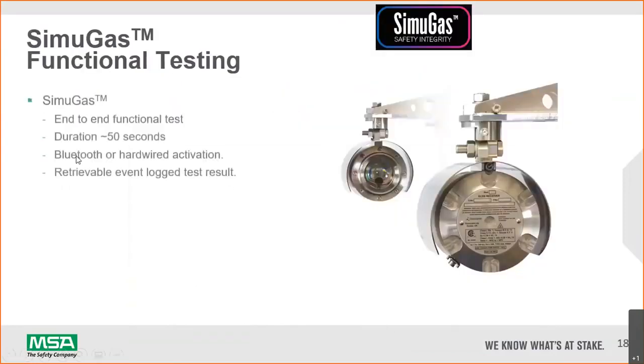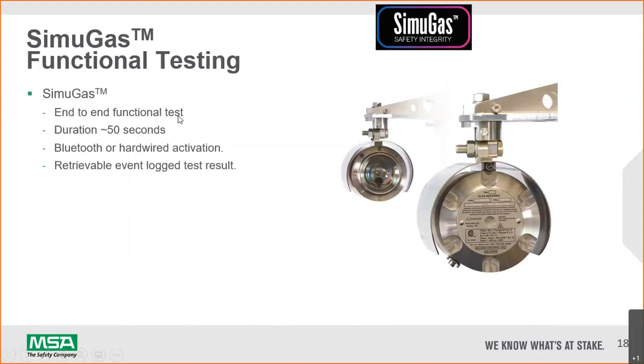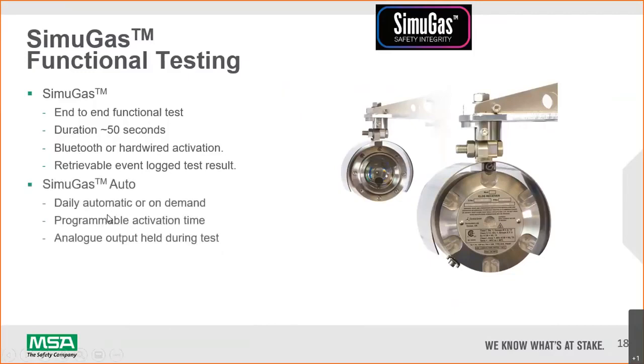This is the SimuGas end-to-end functional test, same like in a piano synthesizer, when you touch a key, it will transmit the same frequency all the time. The duration is less than 50 seconds, with Bluetooth hardware activation and retrieval, that we talked about, SimuGas auto. We call it auto because it happens automatically. But if you want it live at any point, because we have set 10 a.m. every day, but if you go to the field and want to do it at 9 a.m., you can do it. We call that SimuGas live, functional test on demand.